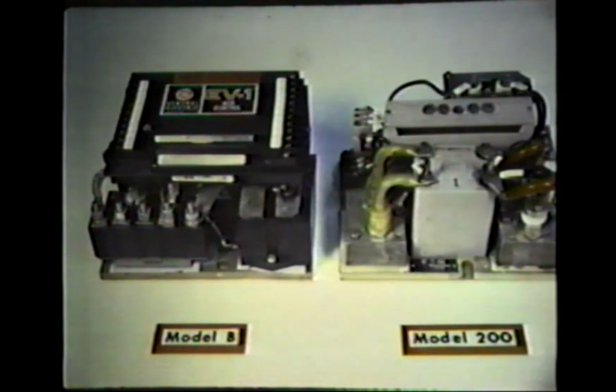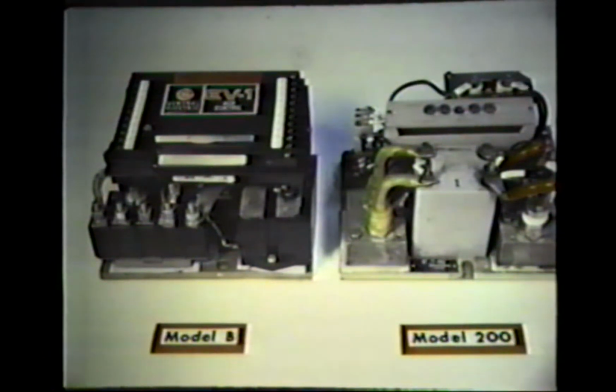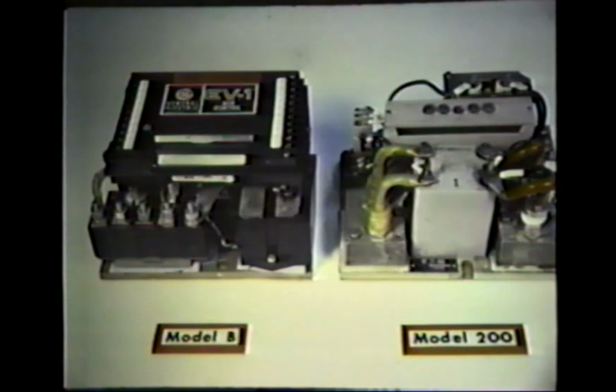The EV-1 and GE Model 100-500 SCR controls are very similar, except that the EV-1 contains standard features that were optional in the former controls. Some of these features are pulse monitoring trip, 1A thermal hold-off, static return to off, and ramp start. The addition of these features significantly changes troubleshooting procedures.